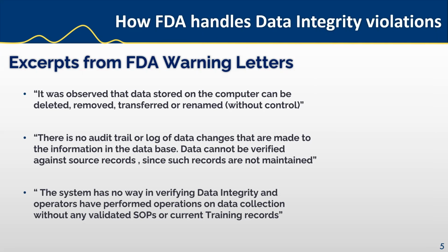Has this data been generated at the appropriate location? Does it have a timestamp? There's no verification, so they cannot relate the data to its original content. The next citation: the system has no way of verifying data integrity, and operators have performed operations on data collection without any validated SOPs or current training records.